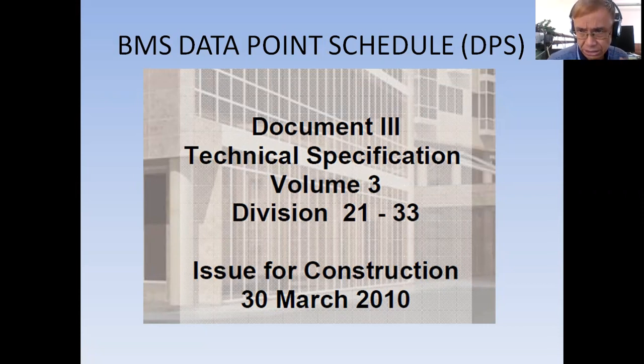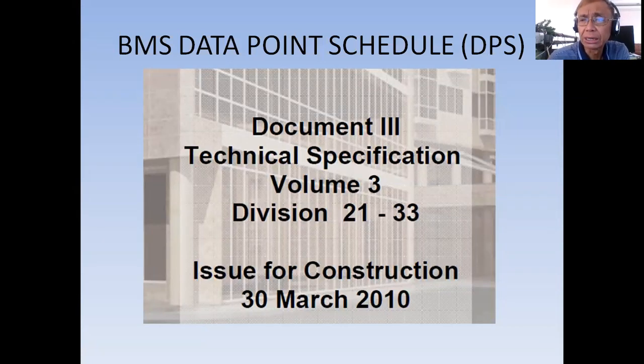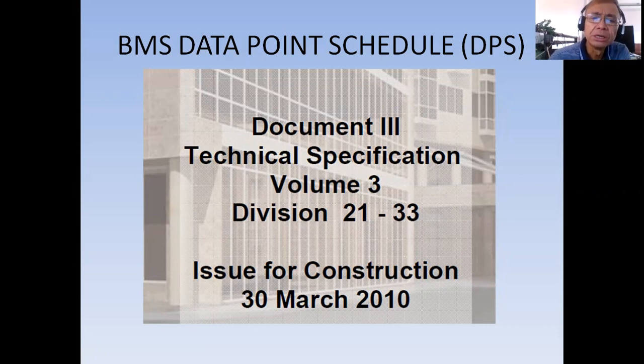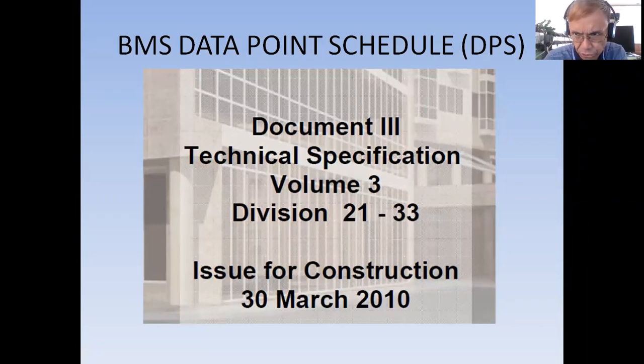This project is a five-star hotel. As you can see on my screen, the document is entitled Technical Specification Volume Three, Division 21 to 33. The specification document is a PDF file composed of thousands of pages. You have to go specifically to the relevant division — in this case, building automation is Division 25. Based on this document you will define and finalize your data point schedule.